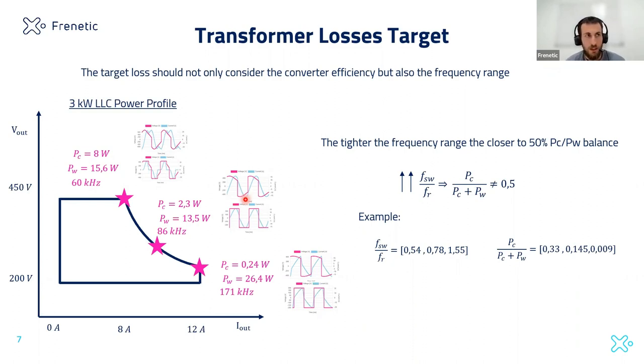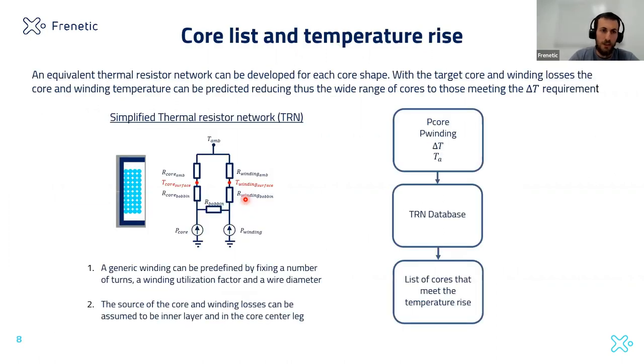And when we are defining the transformer loss target, we should look at the range of frequencies, the closer to unity. So if we have a very narrow range, then the 50% balance could probably be the best way to move. But if we are increasing the range, with a much lower frequency and a much higher frequency, probably we should start looking at a core loss of 40%, 30% at full load.